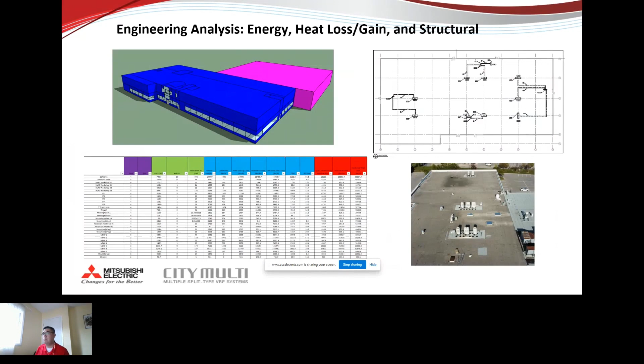And especially, if you recall, we had 90 ton of air source unit, 90 ton of rooftop unit, and we actually replaced that with a 60 ton air source VRF system. So at first I was really concerned because we are going from 90 ton to 60 ton. But coming back to it, well, it's a 90 ton condensing unit and 90 ton rooftop unit that was designed based on the heat loss, heat gain calculation done back then.